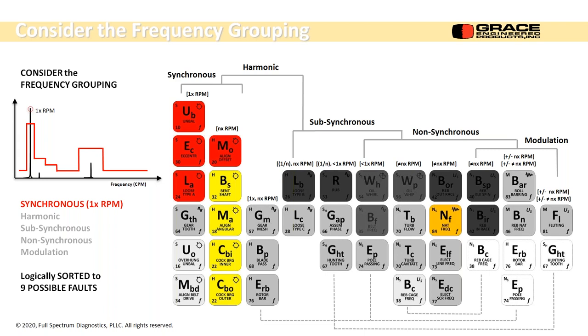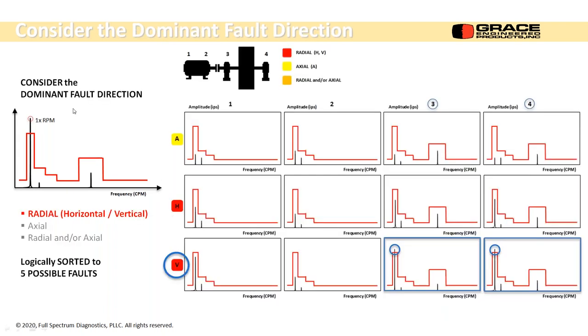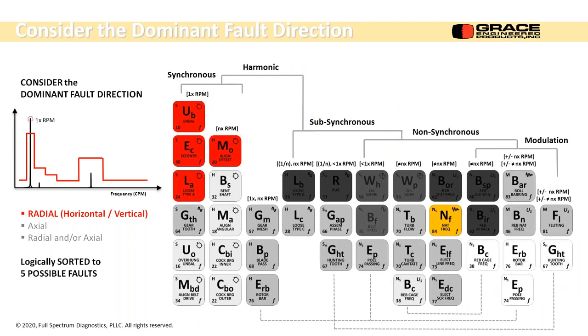We're going to sort by color next, or by direction, dominant direction. And you go back to this, there's no axial vibration, which is nice. So horizontal and vertical, they're radial vibration, and only the vertical one has the alarms to it. So we can say that this is not an axial problem. So the yellow blocks go away. And after just sorting 2 times and removing the faults that are based on design, we're down to 5 different faults that it could possibly be.